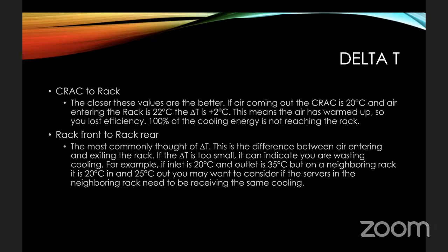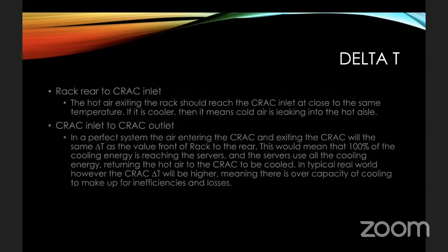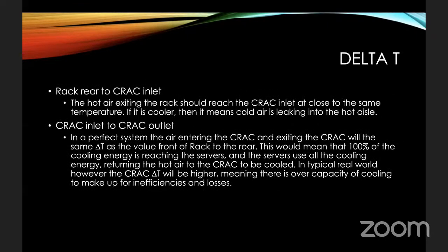So the next delta T to look at is the rack rear to the CRAC inlet. So basically what you can imagine is at every different transition of the air, we are going to monitor the difference between the temperature at the start and the end. So what we're effectively doing here is following the air around the data center. So we went from the CRAC to the rack, we went from the rack to the rear of the rack, and now we're going to go from the rear of the rack back to the inlet of the CRAC.